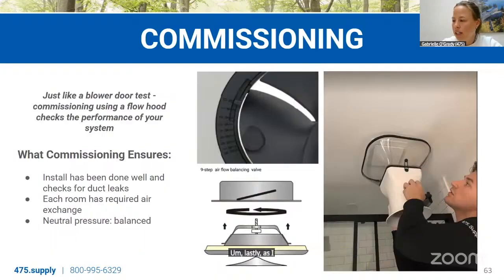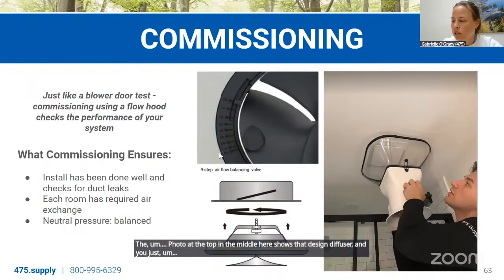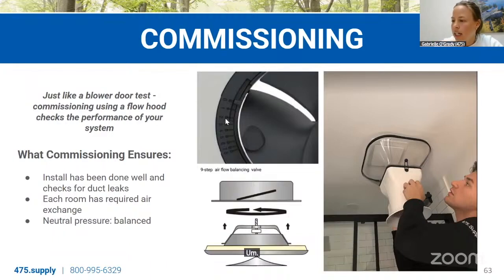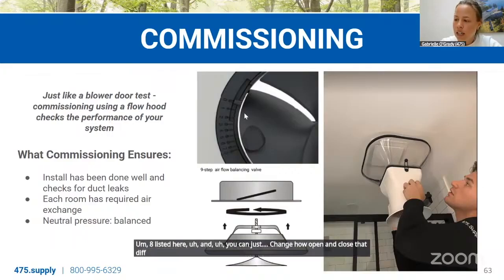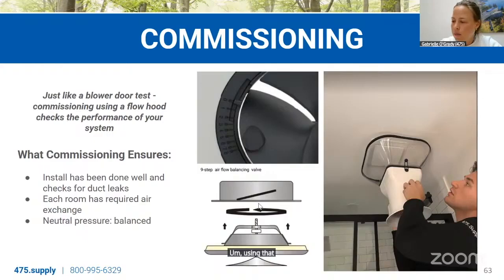Lastly, as I mentioned, you want enough space to allow for commissioning. So as you can see, this flow hood can get directly on top of that diffuser head and allows for very easy commissioning. The photo at the top in the middle here shows that design diffuser, and it has 0 to 8 listed here, and you can just change how open and closed that diffuser is using that. For the metal diffusers, you simply rotate the screw to again change the aperture there as well.